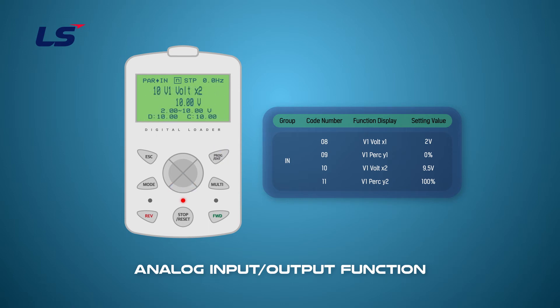Set the maximum input voltage at IN-group 10 to 9.5 volts and set the corresponding input level to 100% at IN-group 11.